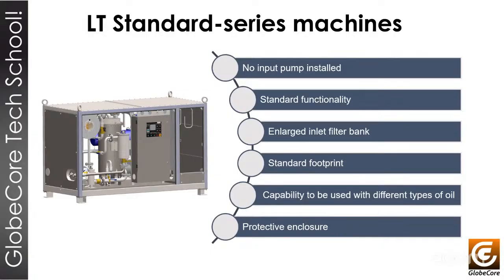Due to the use of more versatile seals, filters, and fillers in the vacuum chamber, the application target includes not only transformer oil, but also turbine oil, industrial oils, natural ester, and other types of oils, which can be worked with this machine with no problem.